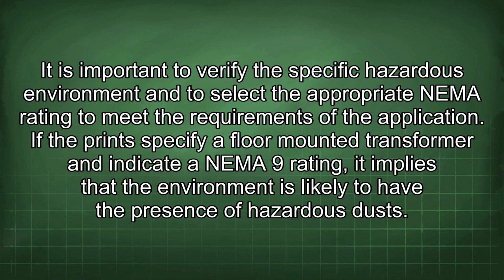It is important to verify the specific hazardous environment and to select the appropriate NEMA rating to meet the requirements of the application. If the prints specify a floor-mounted transformer and indicate a NEMA 9 rating, it implies that the environment is likely to have the presence of hazardous dusts.